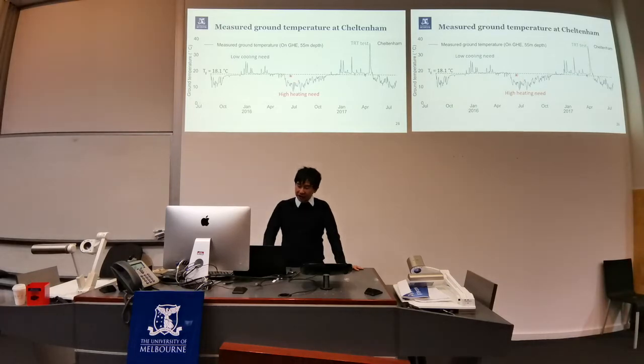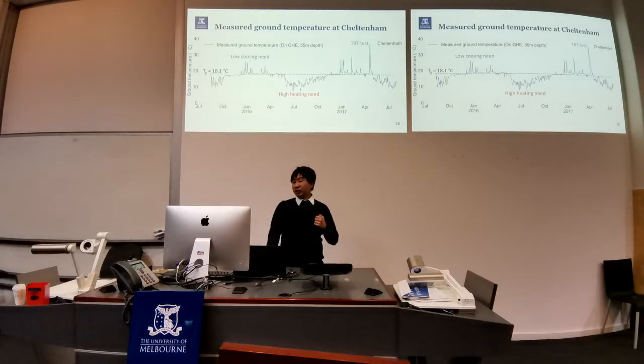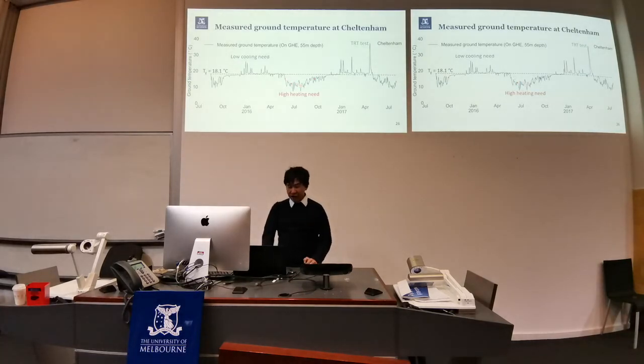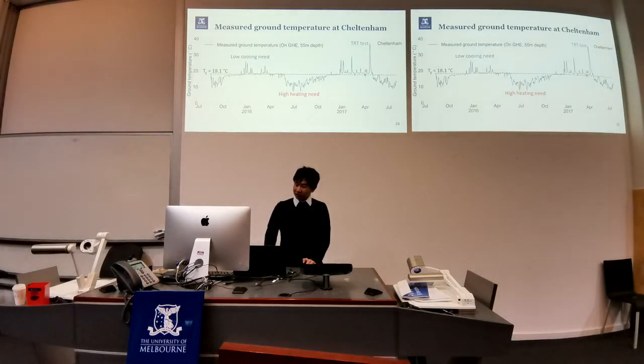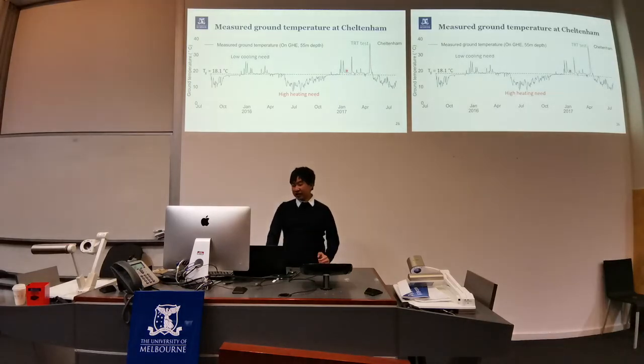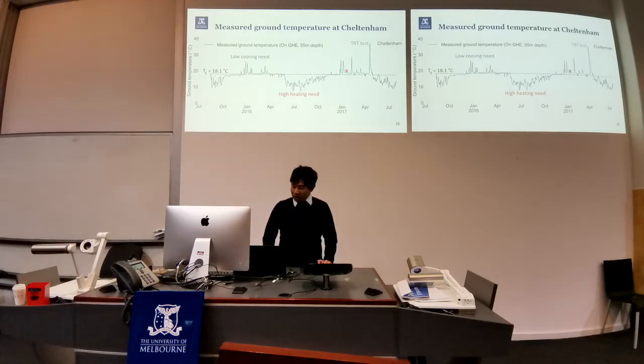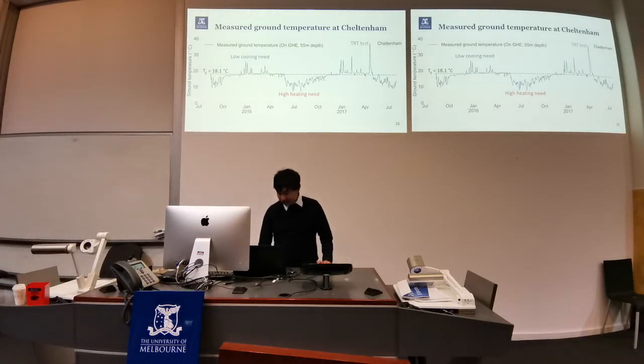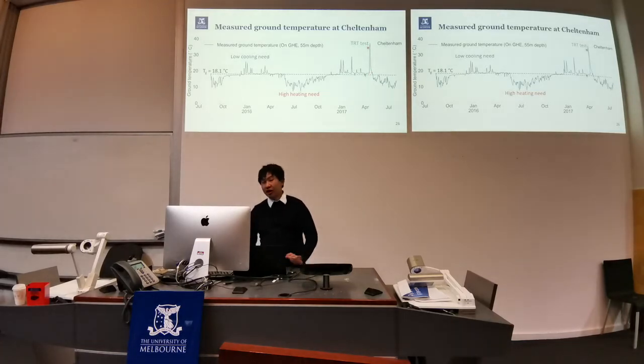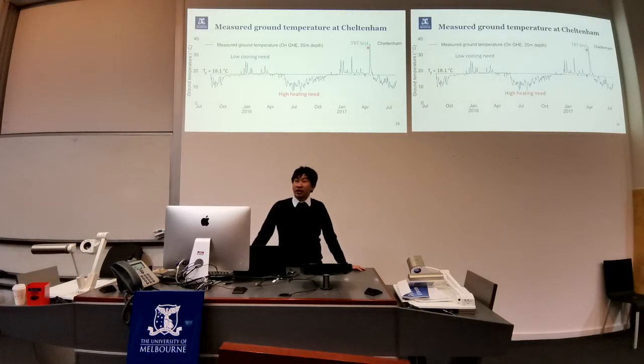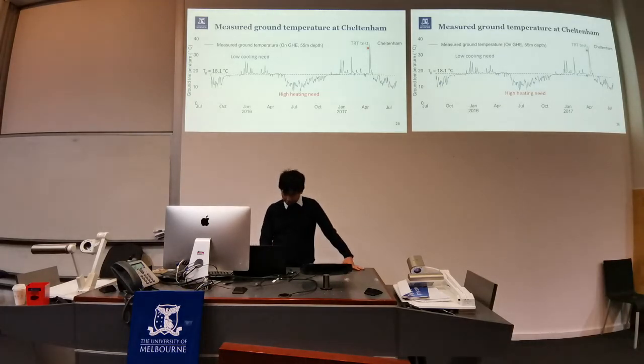As you can see here, in this property during the heating season, as we extract thermal energy from the ground, the ground temperature decreases, and we have a lot more heating use during winter compared to the cooling use during summer. During summer, as you move the heat to the ground, you can see that the ground temperature slightly increases. One exception is at this point, where we conducted a thermal response test with one of our past PhD students. This is when we circulate hot water through the ground for several consecutive days, and that's why the ground temperature increased significantly. This was done to measure the ground thermal conductivity.